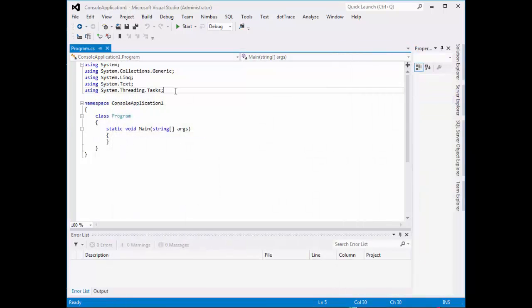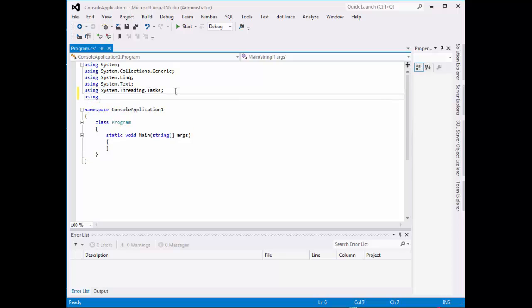So having added the reference to that assembly, we need to specify the namespace. Notice that the namespace includes interop. That's because this is an IVI COM driver, and the COM interface requires an interop assembly to call it. Turns out the interop assembly and the way that's created is also specified by the IVI Foundation, so your COM drivers will include that, and they'll all basically work the same way because the primary options associated with creating that interop assembly are all specified.